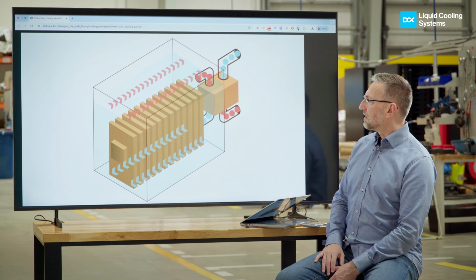I prefer that method, which is basically the immersion tank with the heat exchanger and the pumps located outside of the immersion bath. The heat exchanger would be better, more compact, more dense, more capable, and readily accessible from outside of the tank, not immersed in the tank. The same for the pumps. I can have multiple pumps accessible from outside the tank. I will be able to better maintain, replace, control and monitor them, with fewer challenges and fewer issues. So that's the method which we recommend.